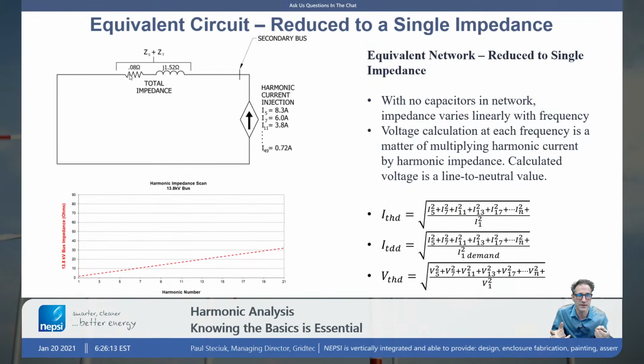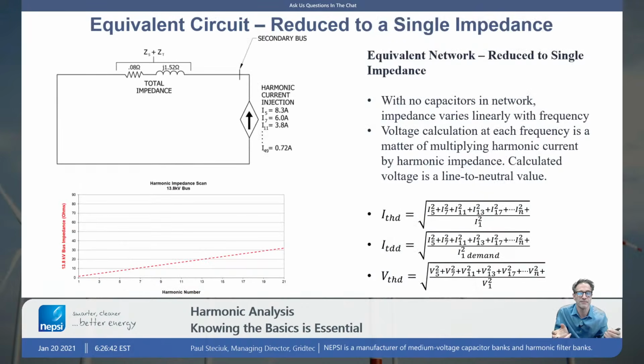And if you think about it, as we go up in frequency, the R value doesn't change. It doesn't change based upon frequency. Now, theoretically, remember that there is the skin effect and there's proximity effect. So harmonics do have a small impact on the resistance in cable and conductors, but the change is small. So for back of the envelope calculations, assume resistance stays the same. And again, you can almost assume that it's negligible here, because at the fifth harmonic, if 0.08 ohms has not changed, the reactance is 5 times 1.52 ohms. It's a lot more impedance.